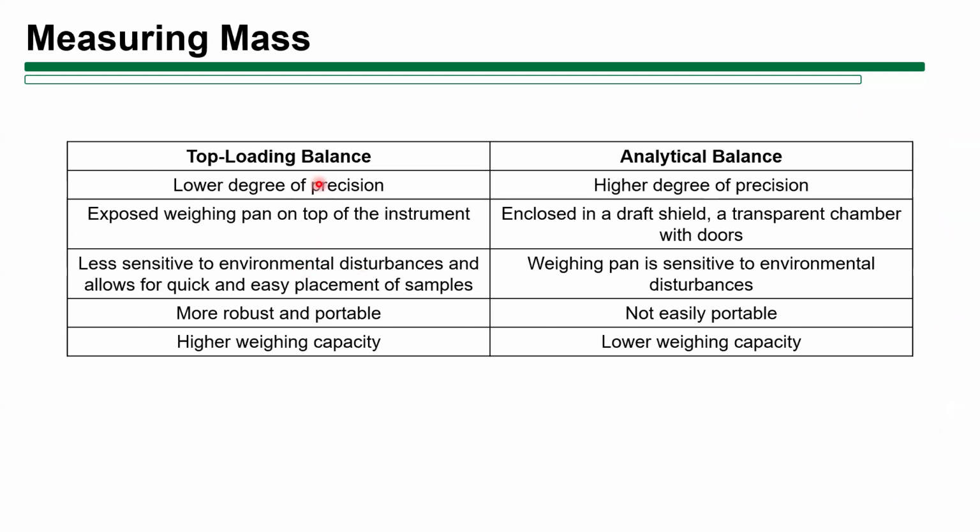The top loading balance is less sensitive to environmental disturbances. All right, and because there's no doors, it allows for quick and easy placement of samples, while the analytical balance is very sensitive to environmental disturbances. All right, and it takes time to put your sample and remove your sample because you have doors that you should open.